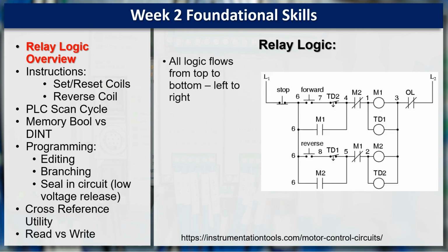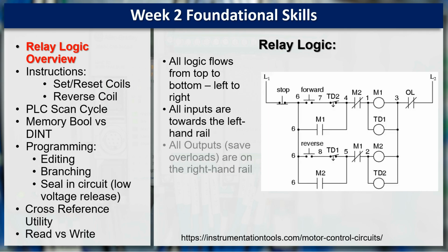With relay logic and ladder logic that followed it, all logic flows from top to bottom, left to right. All inputs are towards the left handrail, and all outputs, save and except for overloads, are on the right handrail. All devices are always shown in their shelf state.